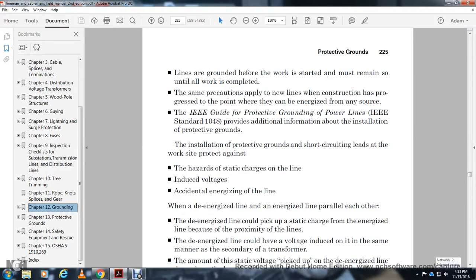Lines are grounded before the work is started, but the grounds must remain until the work is complete. The same precautions apply to new lines under construction, up to the point where they can be energized. See the IEEE guide for the protective grounding of power lines for additional information. Protective grounds are short circuit leads at the work site that protect against the hazard of static charges on the line, induced voltage, and accidental energizing of the line, such as a de-energized line and an energized line running parallel to each other.